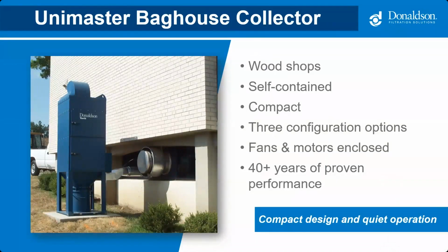Now, the Unimaster. It's self-contained with everything needed to begin collecting for a wood shop dust collector. The fan and motor are there. There's an automatic shaker, a shaker motor, and system controls. The installation is quick and easy. It is compact, so it doesn't take up a lot of floor space, but it is intermittent duty. It needs to shut off to clean.